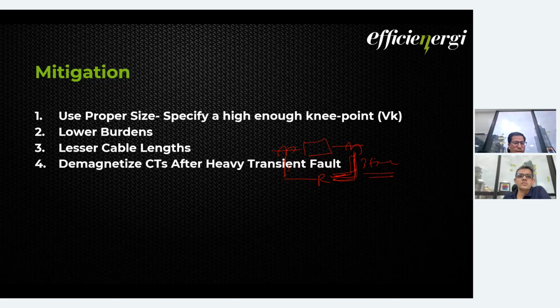Then you have to demagnetize the CT after a heavy transient fault. If there is a heavy fault in your facility, you have to remove all the magnetism, the remnants in the core. Otherwise, on the next operation the CT will saturate heavily because it is already magnetized. So that is one thing you can do. I'm running late, so I will keep the remnants for next time, because I wanted to explain them in more detail.